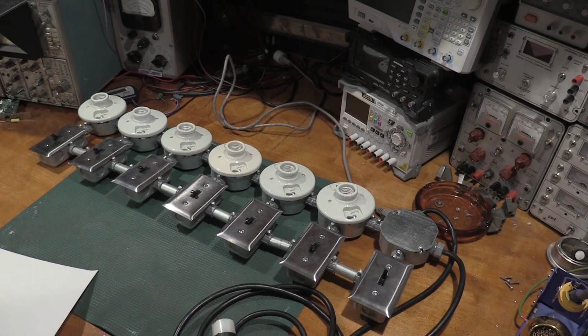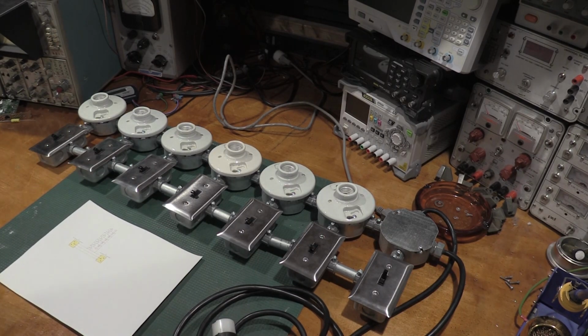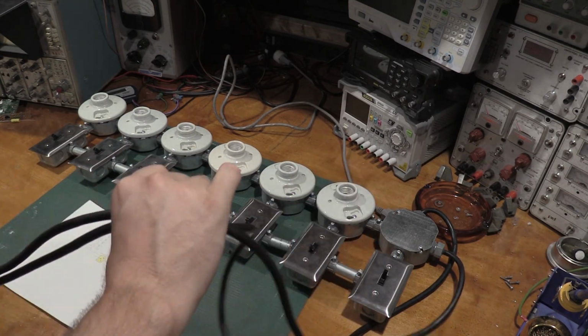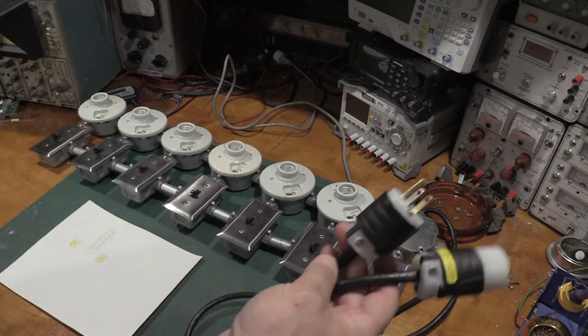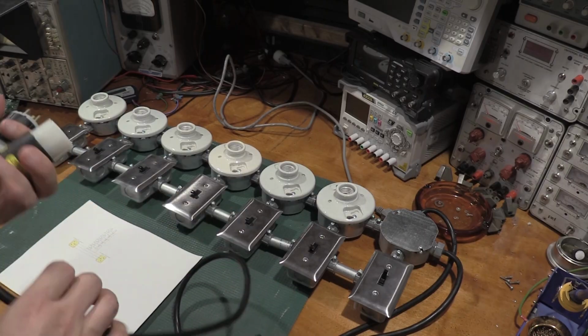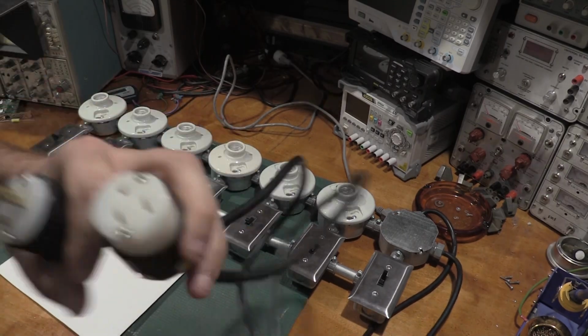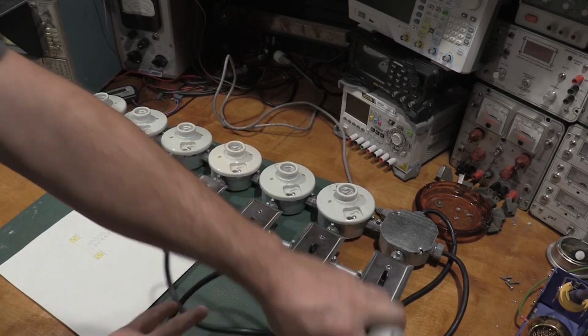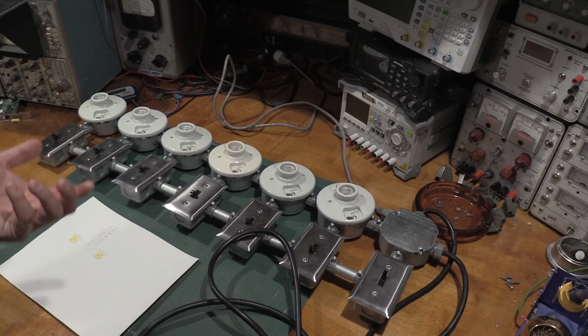These are 15 amp cords and plugs, given that these are 14 gauge. And if I ever needed more than 15 amps on this, I could easily swap these out, get some new plugs. If I'm doing devices under test that need more than 15 amps, I'm doing special cable anyway. That's getting into some of the significantly heavier pieces of equipment when you start drawing 20 amps plus.